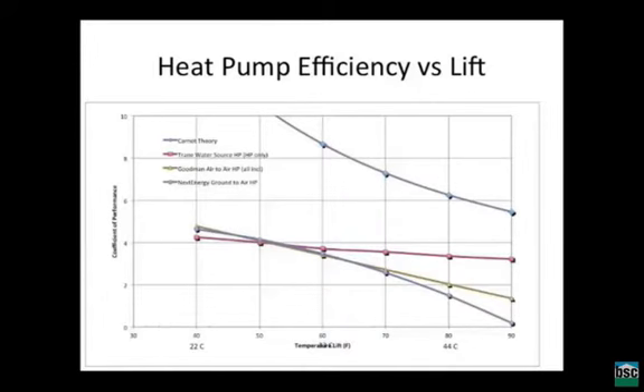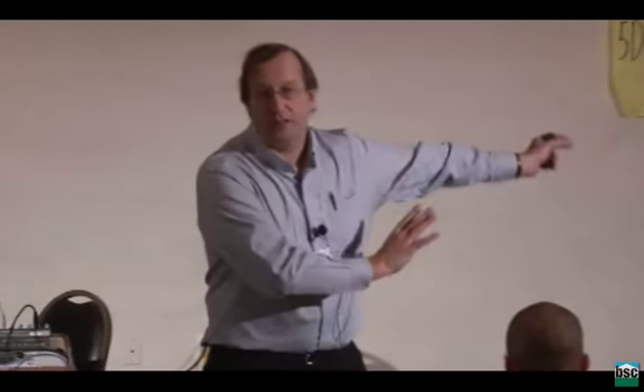Okay, so here is your standard outdoor coil that rejects or collects heat. In air conditioning mode, that coil on the left side of that Lennox unit warms up, warmer than the outdoor air, and then it rejects heat to the outdoor air and you cool the building inside. In heat pump mode, it will be colder than the outdoor air, and so heat will flow from the outdoor air to the colder coil, and that heat then is pulled in and shed into the building to heat it.